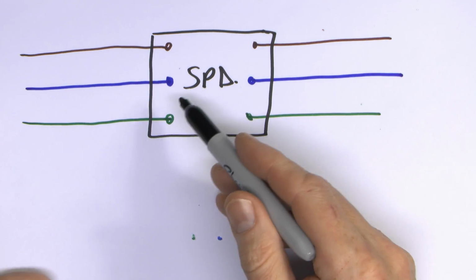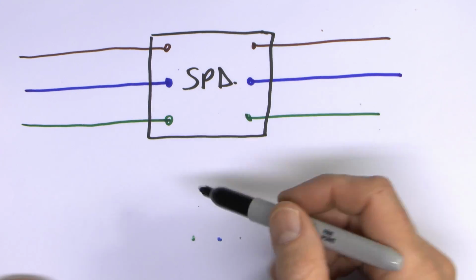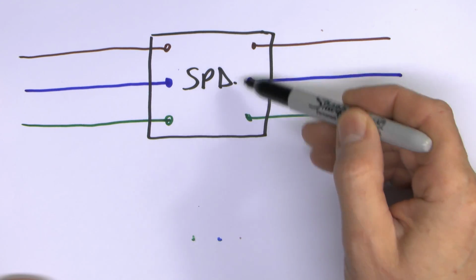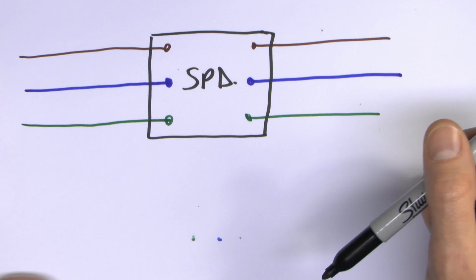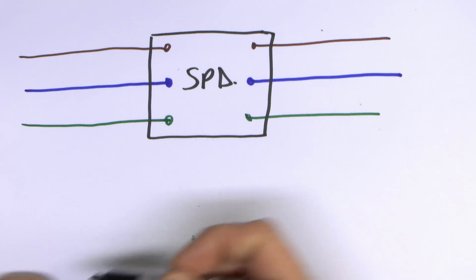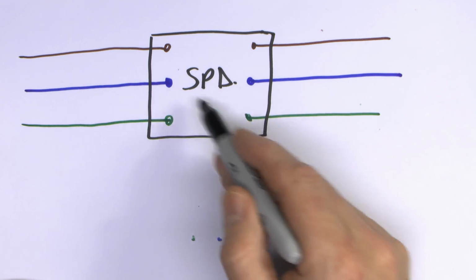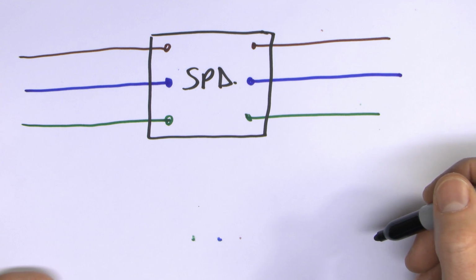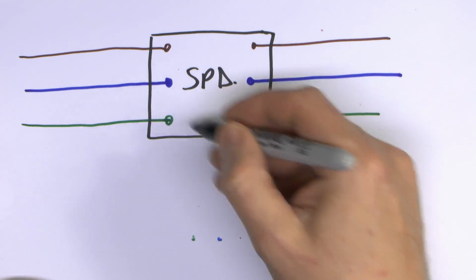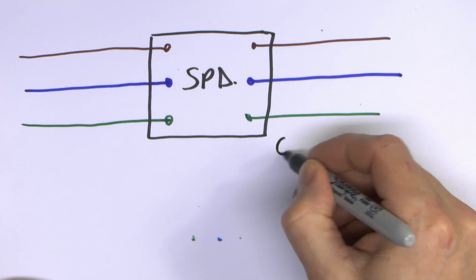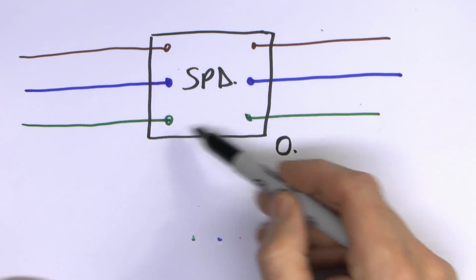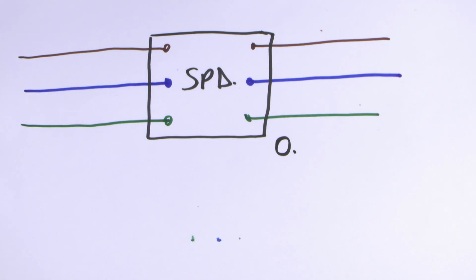And in the case of this, again, the distances involved are pretty much 0. It's just any sort of internal connections within the surge protector device or whatever you've got there. So again, supply coming in, surge protector device in the middle, and then going out to your consumer unit or whatever. And again, in this case, the measurements, distances are pretty much going to be 0, because it's all contained within the same thing in there.